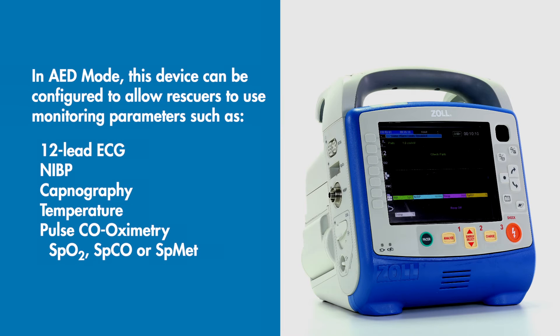In AED mode, this device can be configured to allow rescuers to use monitoring parameters like 12-lead ECG, non-invasive blood pressure, capnography, temperature, or pulse co-oximetry, including SpO2, SpCO, or SpMet.